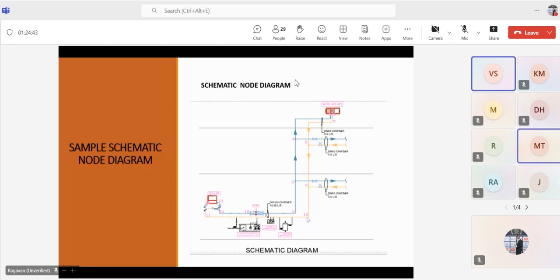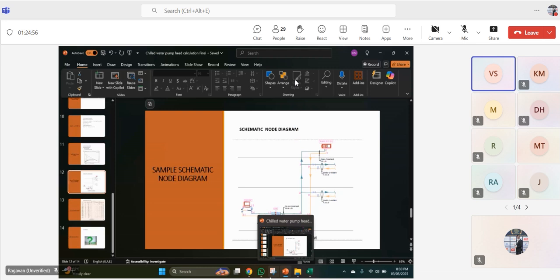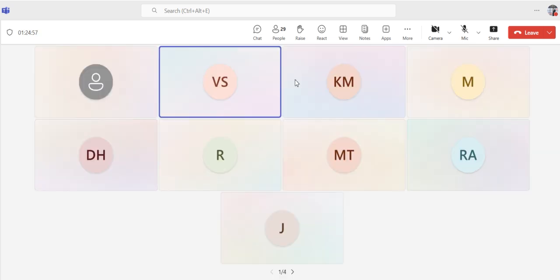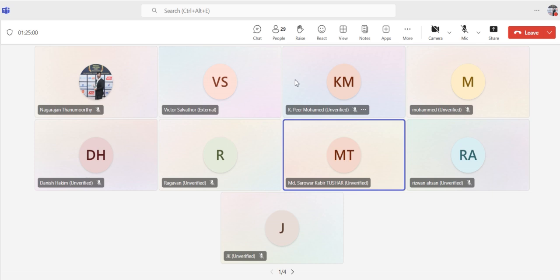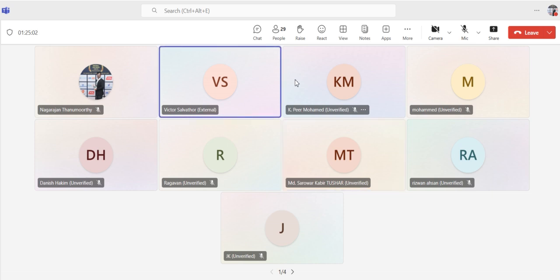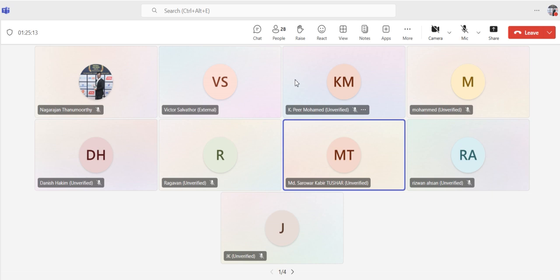Okay, sir, got it. Because you have to calculate both separately, because the routing is like this, right? In between you have the bypass line. That is a separate case. Based on the flow rate, it will open and close. The loop is between the chiller and the secondary pump, and the primary pump is in between.